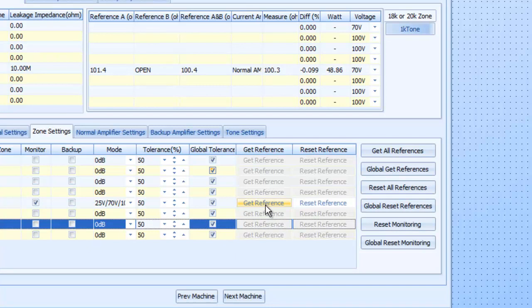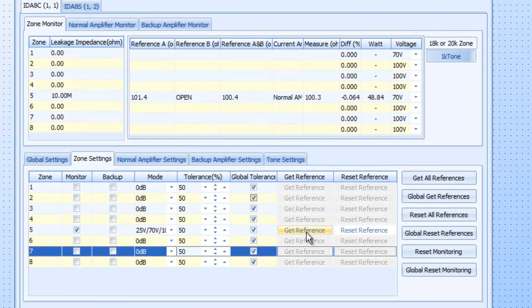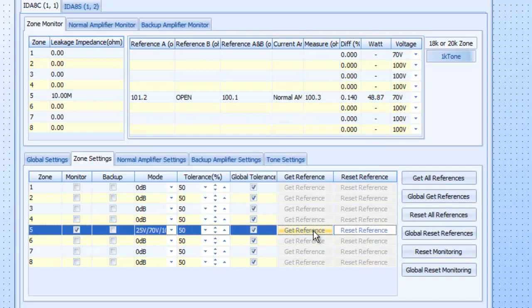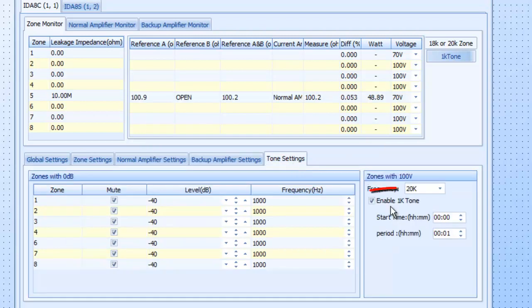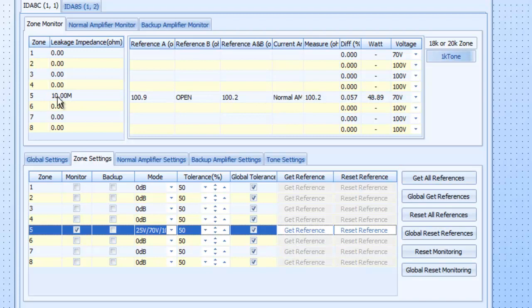And also global get references will be, you're going to get all the global references and reset. We'll get back to that in a second. But first of all, let's just do a get reference for circuit number five. So I'm going to click here and hopefully you heard the one K double beep tone. That was because we enabled the one K tone in our settings. That's done. And as we can see right here, the leakage is fine. We're at 10 mega ohms. There's no leakage going on.